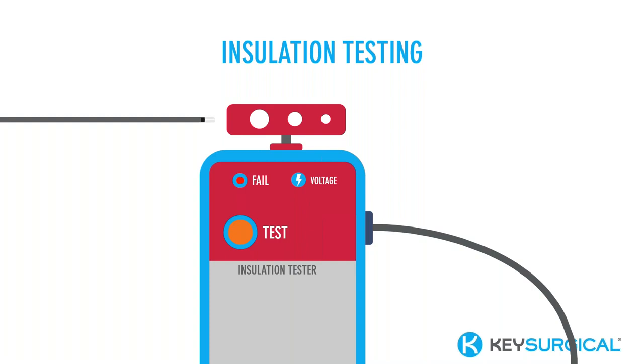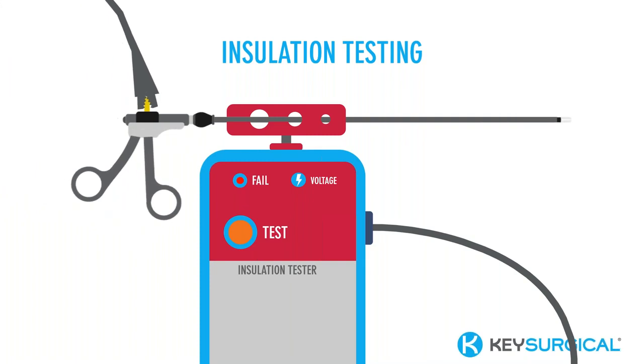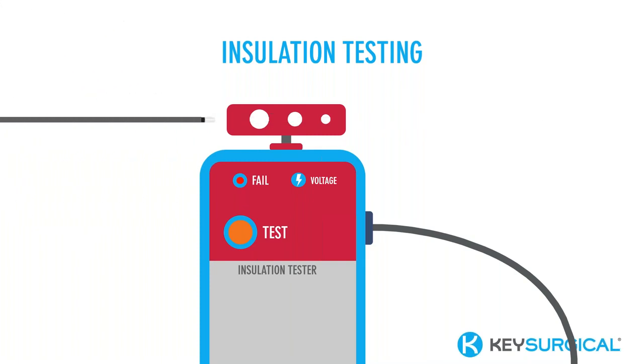So here's an example of a laparoscopic instrument being put through a tri-ring. Make sure the full shaft gets run through the tri-ring. Find the right spot for the diameter of the tool you are running through the insulation tester. It should fit but not be snug. Do not force the instrument through the spot. You may actually produce damage on that insulation.